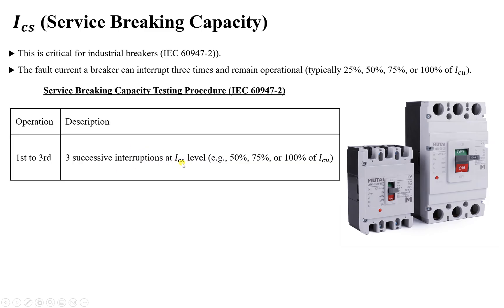To test ICS per IEC 60947-2, they perform three successive interruptions at ICS. They apply different fault levels — for example 50%, 75%, and 100% of ICU — depending on what the breaker is designed for. This gives three different faults to confirm the breaker is properly rated. This is the testing procedure used to certify compliance with IEC 60947-2.